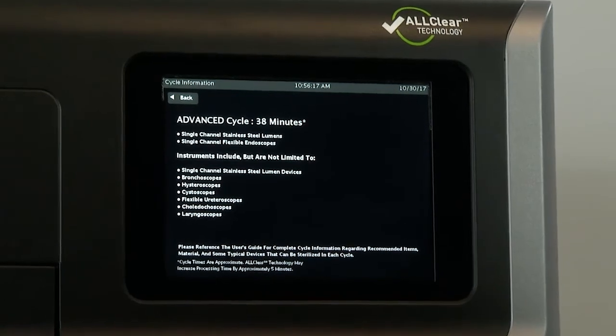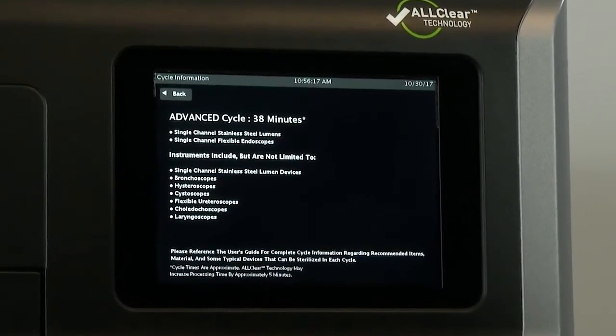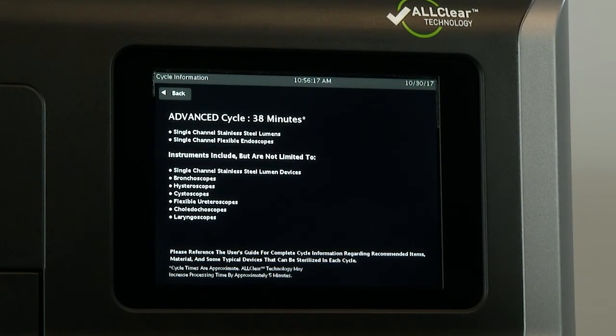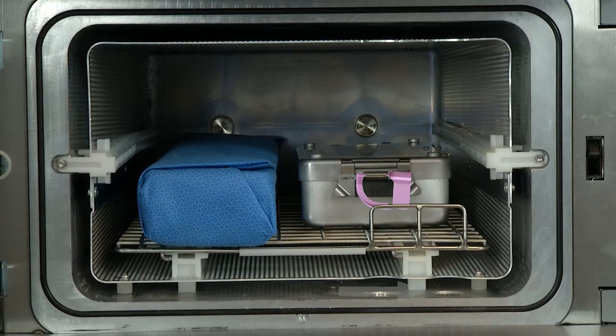The screen will display information about the cycle and a list of items that can be sterilized in the selected cycle. When placing the load on the shelves, do not block the ultraviolet lamp beam in the front side of the chamber. Ensure the load is centered on the shelves and that the shelves are centered in the chamber. Do not allow metal objects to come into contact with the walls of the chamber, the door, or the electrode. Contact with the walls, door, or electrode can cause a cycle cancellation and/or damage the item or the sterilizer. Leave at least 1 inch or 25 millimeters of free space between the load and the electrode.